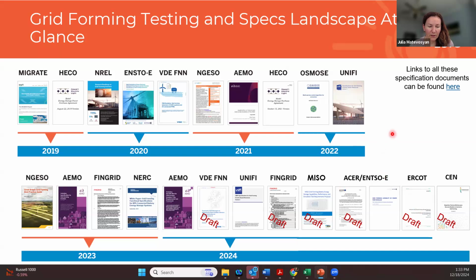ENTSO-E is the Association of System Operators in Europe. Since 2019 as an effective date, they have requirements for all inverter-based resources, or all generation resources in Europe that are part of ENTSO-E. The requirements are harmonized across ENTSO-E member states. Now they have an update in the works that will require future inverter-based resources to be grid forming as well, but this hasn't been approved yet and is currently with the European Commission for consideration.